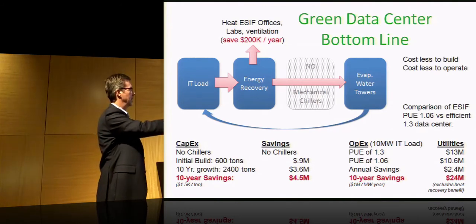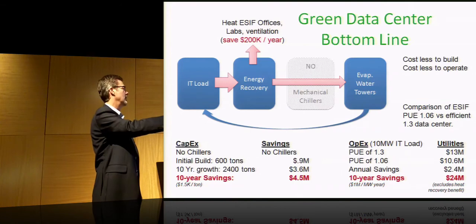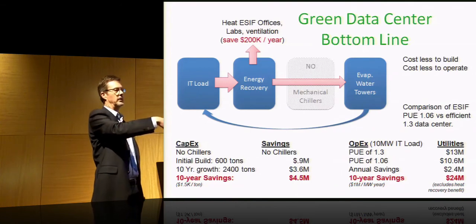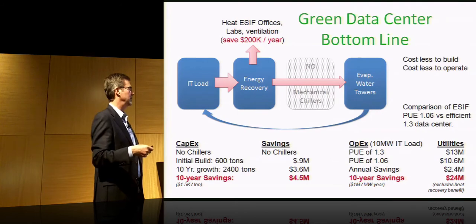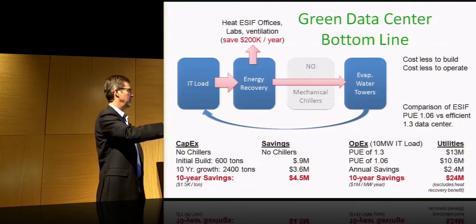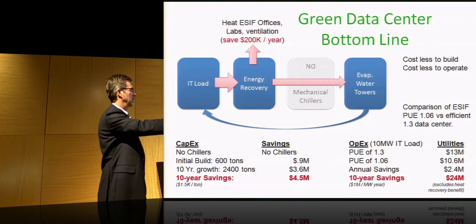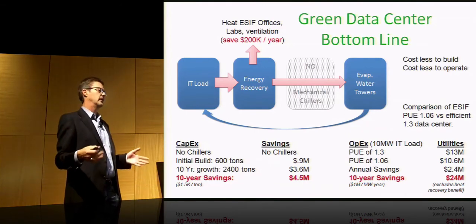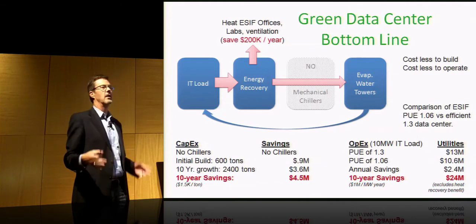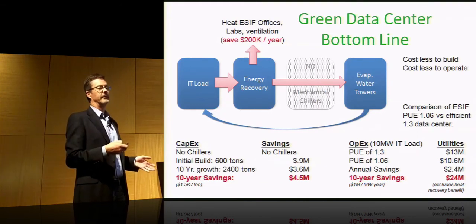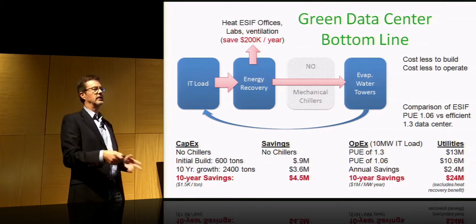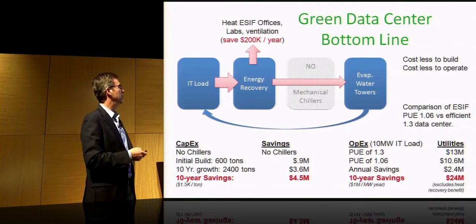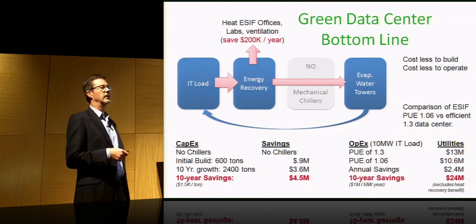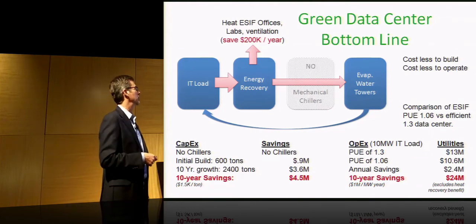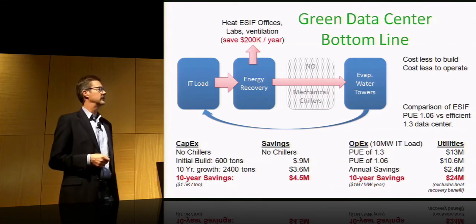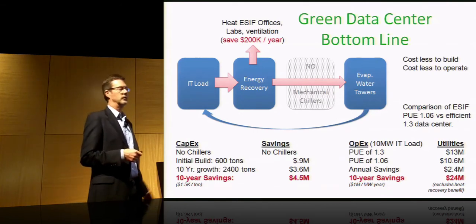So if we compared a 10 megawatt load and assume we pay $1 million a megawatt, and we compared our PUE of 1.06 with an efficient data center running at 1.3 and a 10-year savings, we're looking at $24 million of savings for our efficiency. And this does not include the savings that we offset by capturing heat and reusing it. This is just on the energy side. We save about $200,000 a year by not having to heat the building from our central plant. So if we add that in, over a 10-year span, it would be another $2 million.